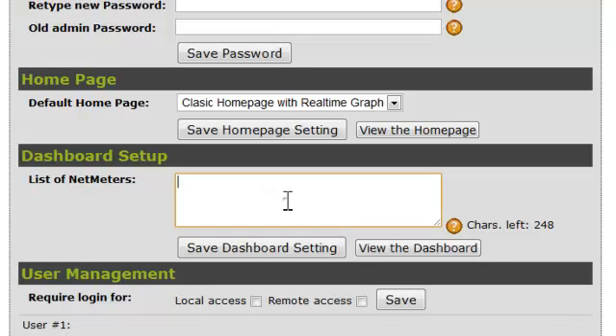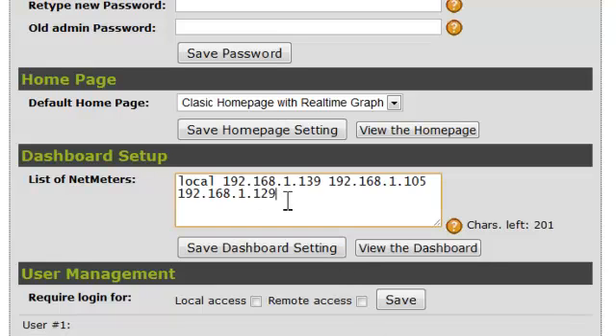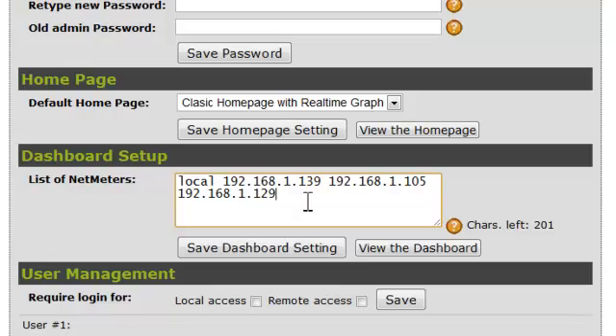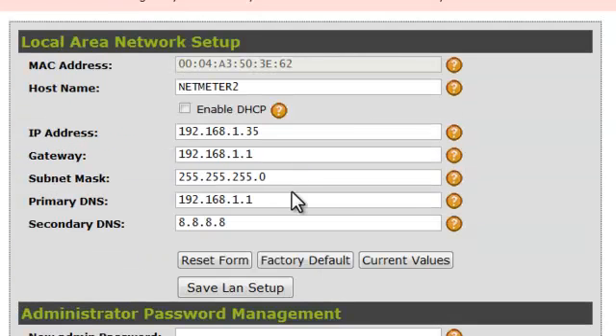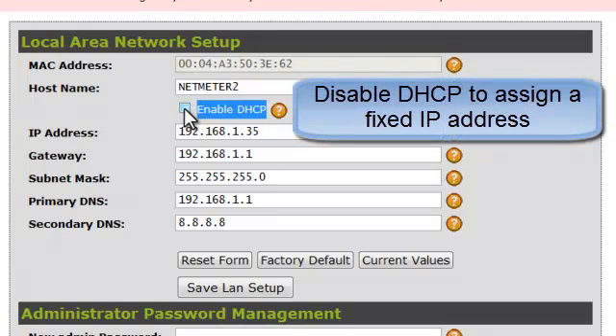You can enter either IP addresses or addresses that are provided through the default domain name server. However, you cannot use the NetBIOS addresses such as the default NetMeter name like you would use when accessing a NetMeter through your web browser, as described in the user manual. For most NetMeter installations, it is recommended that each NetMeter be assigned a unique fixed IP address in order to avoid the possibility that the IP address may be changed dynamically by the DHCP server.